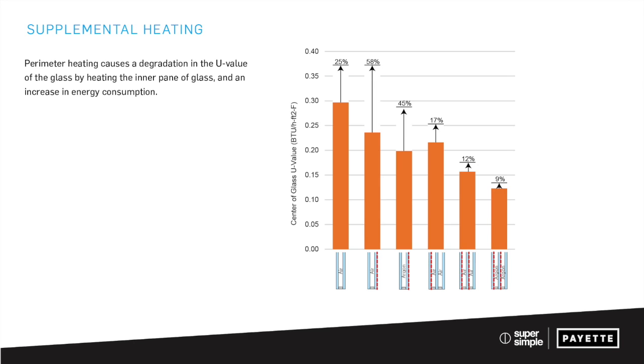If you want to design a building with lots of glass, you end up realizing the glass is going to be cold, so you have to put in a radiant supplemental heating system — which is super inefficient, wastes energy, and is expensive. Perimeter heating also reduces the effective U-value of the glass whenever it's on, because heating up the glass removes the resistance you get from the air film between the surface and the room.